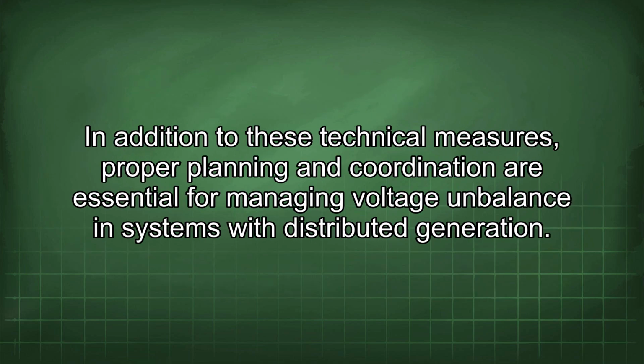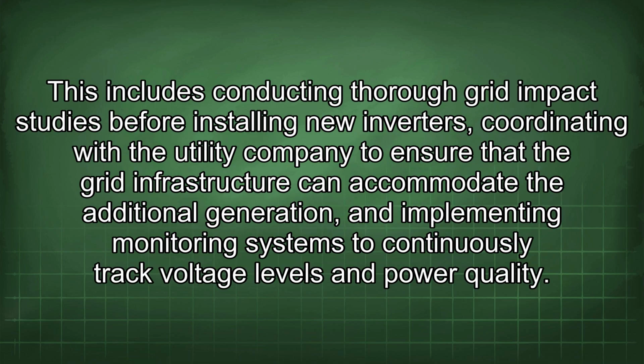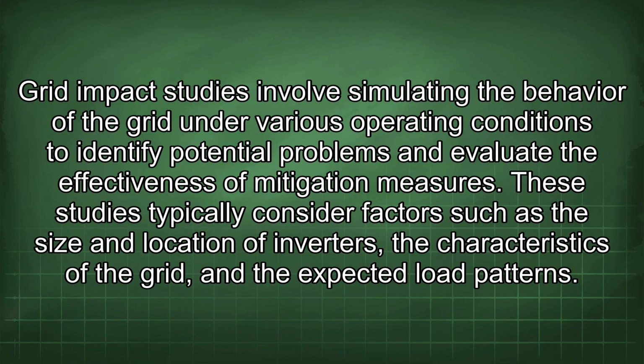In addition to these technical measures, proper planning and coordination are essential for managing voltage imbalance in systems with distributed generation. This includes conducting thorough grid impact studies before installing new inverters, coordinating with the utility company to ensure that the grid infrastructure can accommodate the additional generation, and implementing monitoring systems to continuously track voltage levels and power quality. Grid impact studies involve simulating the behavior of the grid under various operating conditions to identify potential problems and evaluate the effectiveness of mitigation measures.